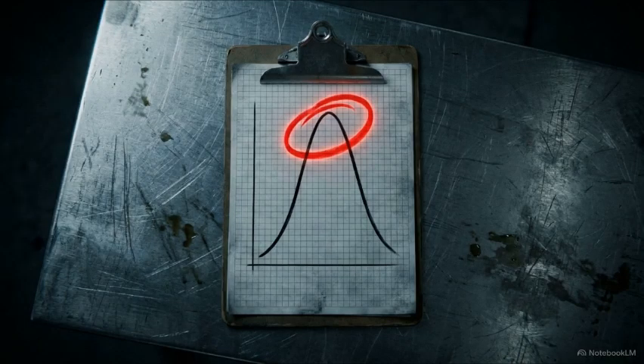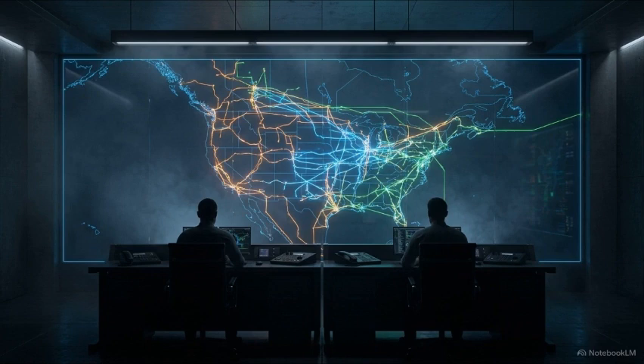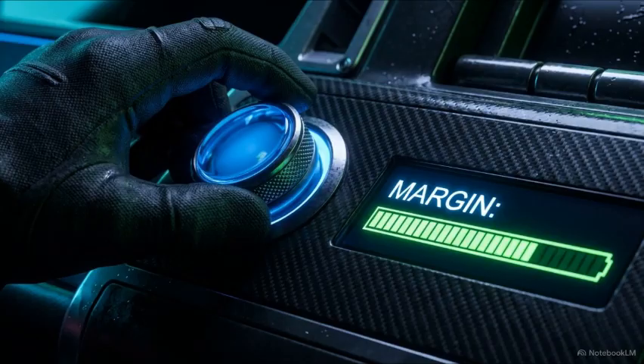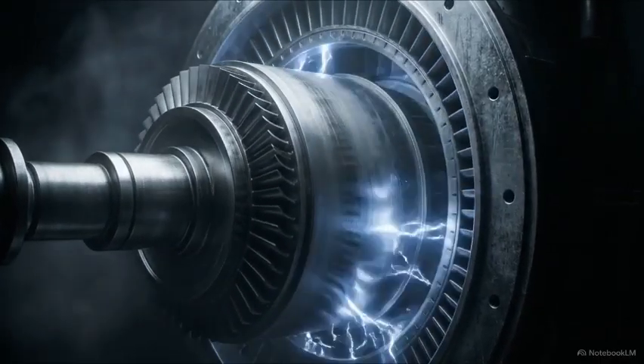To prevent this 90-degree collapse, engineers have to artificially force the system's maximum power transfer capability, called Pmax, as high as possible. A continent-spanning power grid survives vast distances because operators actively manipulate the system's variables. They carefully engineer the grid to widen the gap between normal daily operation and catastrophic failure. That manipulation starts directly at the source.